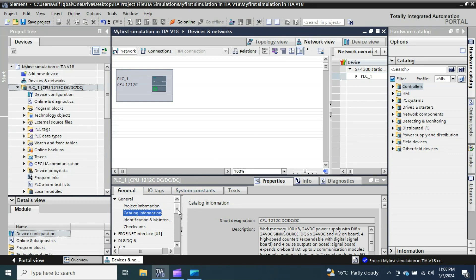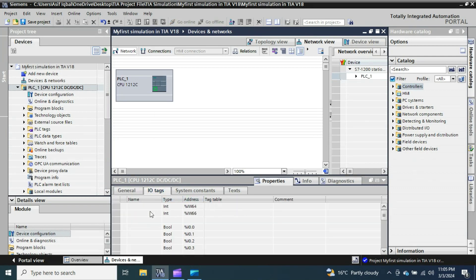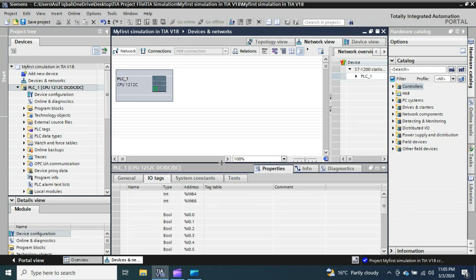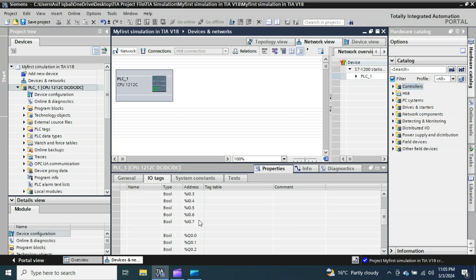You can see information about the CPU 1212C DC/DC/DC. This is a very good feature of TIA Portal — it tells you how many inputs and what kind are available. This CPU has two analog inputs starting at address IW64 and IW66, digital inputs from I0.0 to I0.7, and digital outputs from Q0.0 to Q0.5.